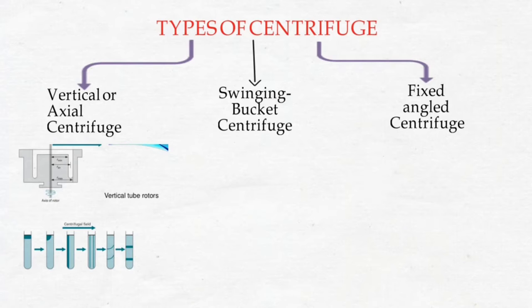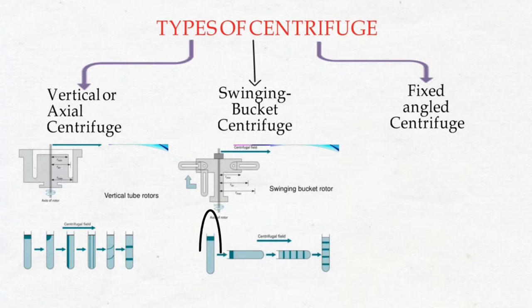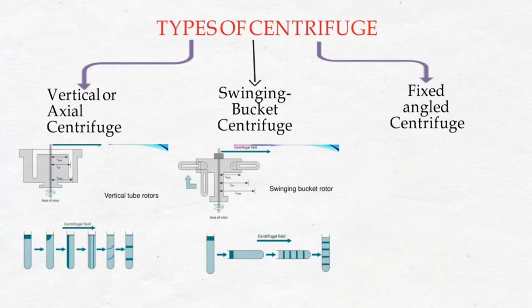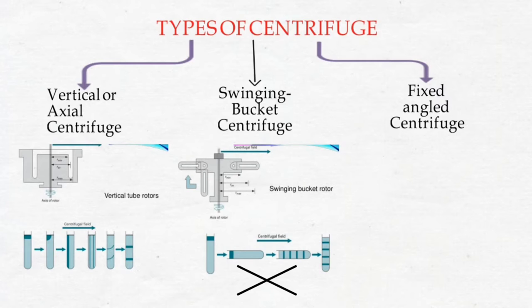In the swinging bucket centrifuge, the tubes are in a vertical position when the centrifuge is at rest and assume a horizontal position when operating. The longer distance of travel allows better separation, so it is mainly used for density gradient centrifugation. A speed of more than 5,000 RPM is not practical in this type.